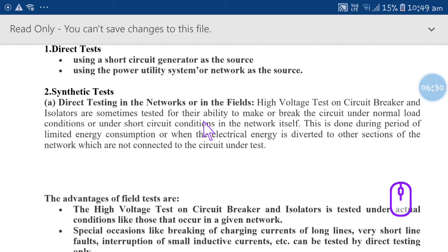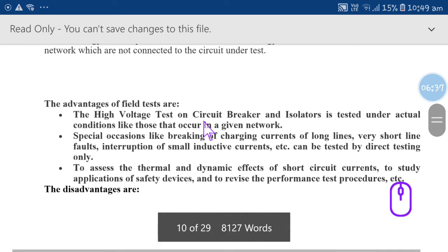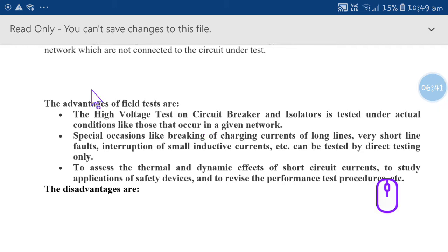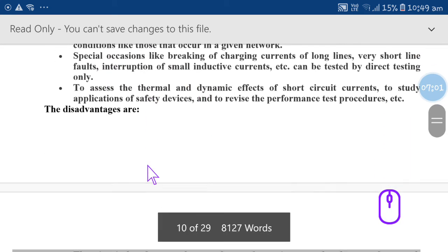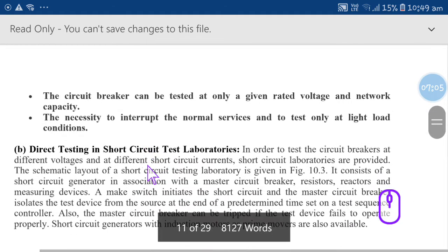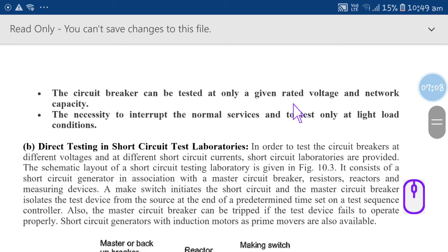Apart from that, circuit breakers and isolators which are not connected in the field are first taken out, tested, and afterwards connected. That is the direct test. The advantage of this direct, field test is that the high voltage tests on circuit breakers and isolators are done under actual conditions, of a particular network, okay. They will test how much actually takes place in circuit breakers and isolators, okay. Making and breaking of charging current, they will see how much of that small inductive current and capacitor current, all those things they will check, okay. And safety also plays a very important role. Disadvantage: the circuit breakers can be tested only at a given rated voltage, and also network capacity, you can call it, okay. And it is also necessary to interrupt normal services, okay, and light load conditions also, okay.